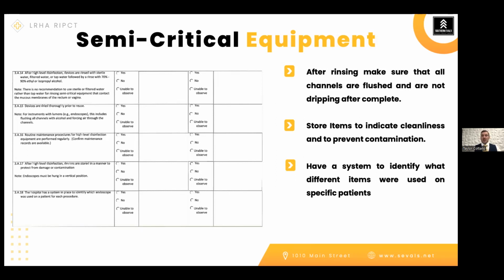And for our endoscopes, whenever we hang those, we need to hang those vertically. When it comes to vertical hanging, a lot of folks may have closets, either pre-built closets or standalone closets. Those endoscopes are supposed to be not in contact with the side walls or the floor. You want to make sure that they are hung vertically, and you can indicate that they've been cleaned either through a tag system or through a log of when you were able to clean those.